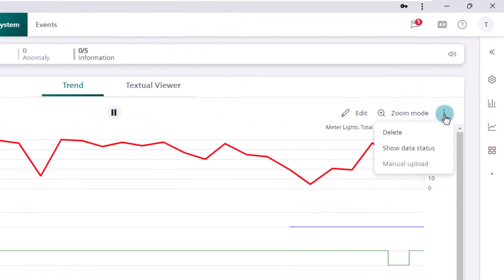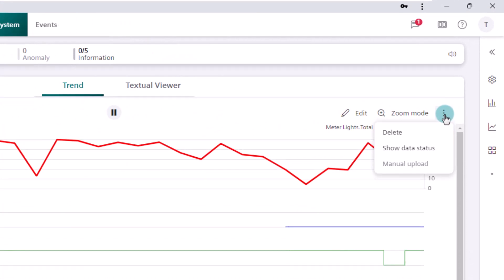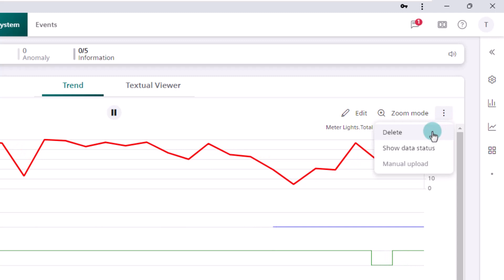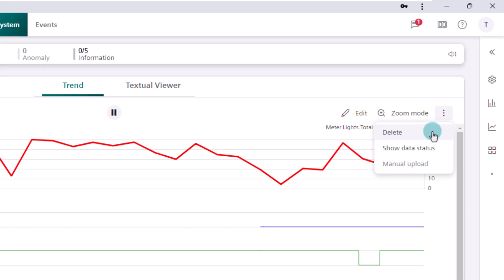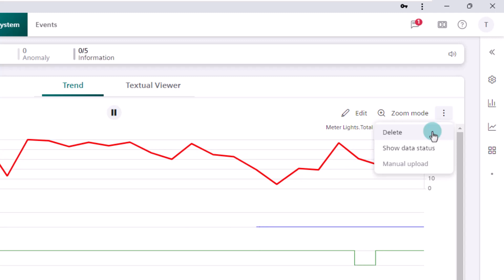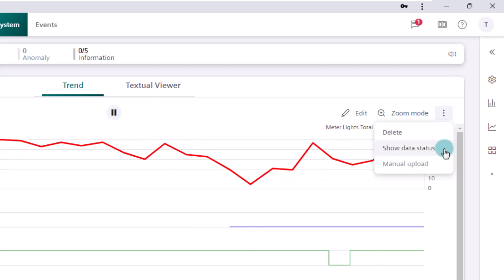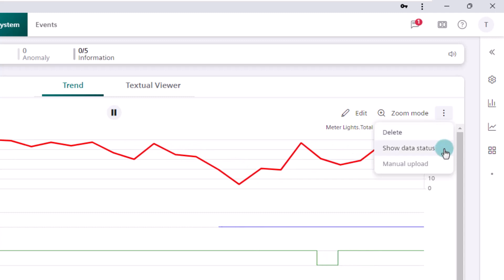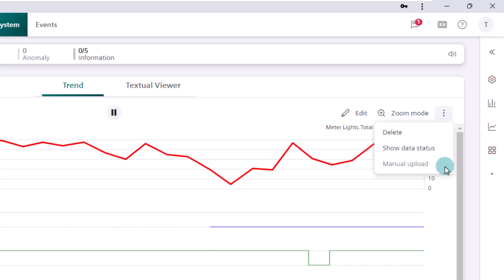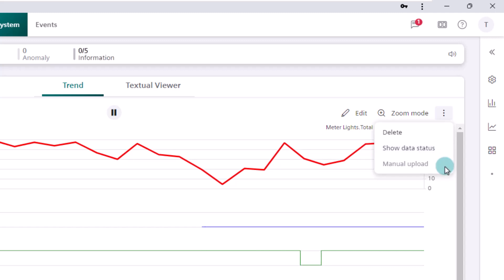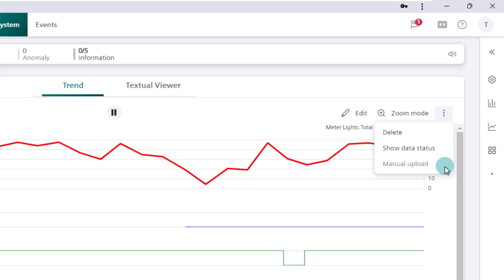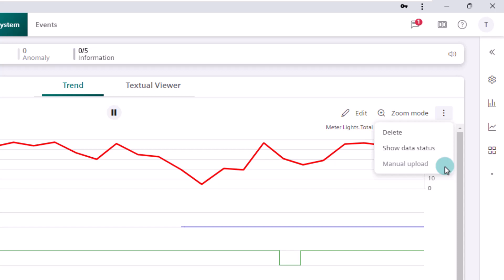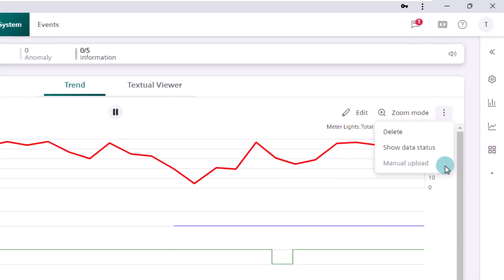The trend view offers us the following options, which only apply to the selected object. Deleting the object is only possible for online and trend view definition objects, because these objects are created in the Desigo CC system. BACnet offline trend objects cannot be deleted. The feature show data status will be explained in the sub-chapter quality attributes. The last option, manual upload, fetches the latest data of all the BACnet trend log objects and displays it in the chart. This option is enabled only for trend log or trend log multiple objects, or if the selected trend view definition contains offline trend log objects or trend log multiple objects.